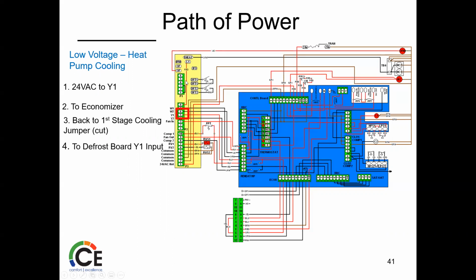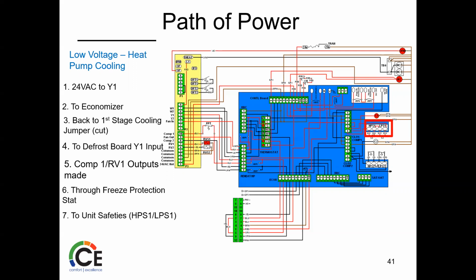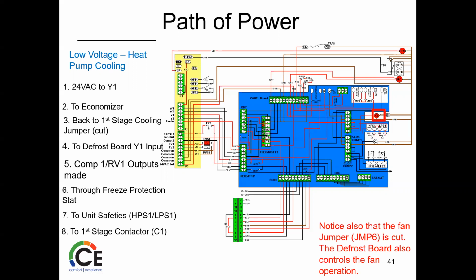But at that point, now it's going over to your defrost board, and this board is going to start to take control of what's going on here. So the defrost board gets a Y1 input, compressor one, RV1 outputs are made down here. Looks to make sure the freeze protection status is closed. Checks the high and low pressure switches. And then off we go. And of course, also the fan, that jumper 6 is going to be cut. The board now controls the fan instead of it getting a direct call through the main board.